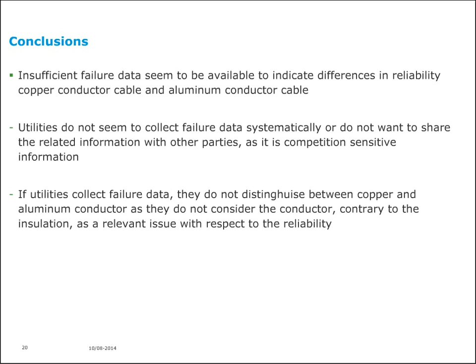Copper conductor cables are preferred technically because of lack of problems with connectors, ease of installation, better mechanical properties, and smaller radial size. For that reason, there are still all-copper utilities that say they only want copper conductor cables because it's better. However, we have to admit their number is decreasing.